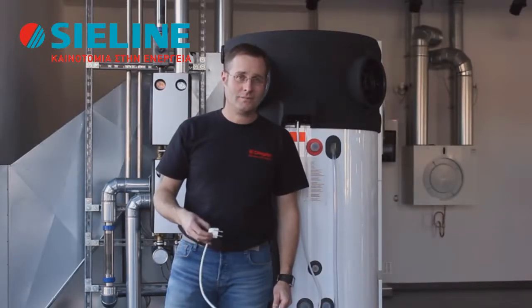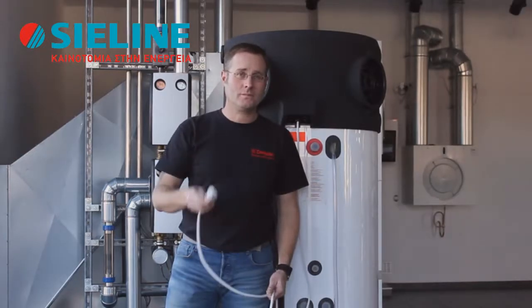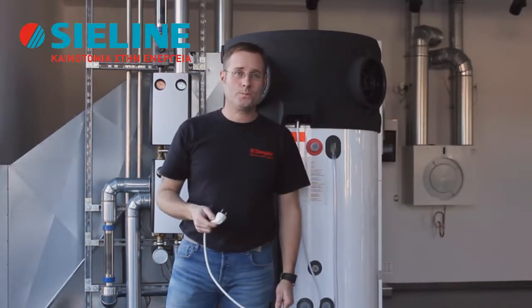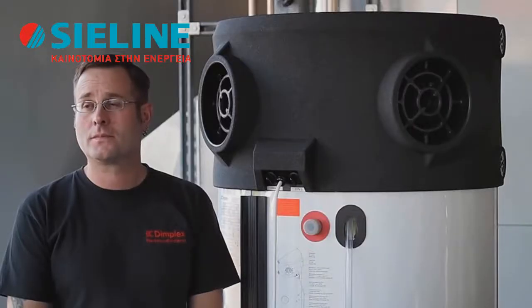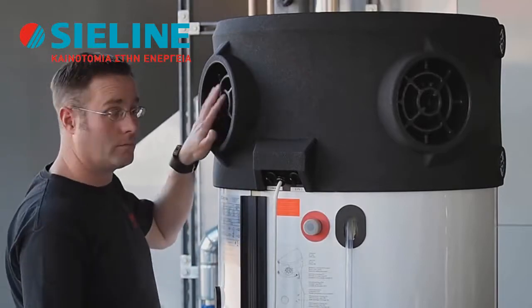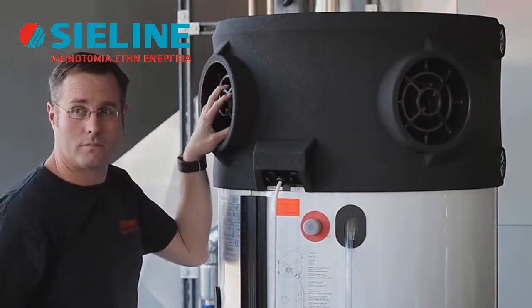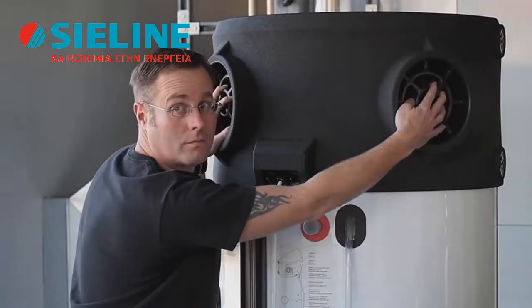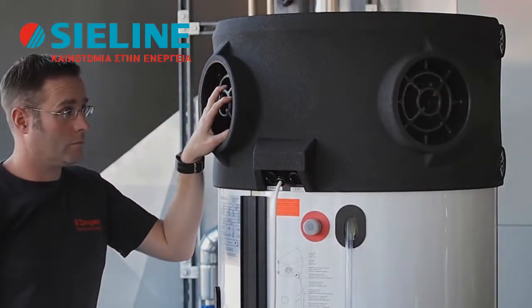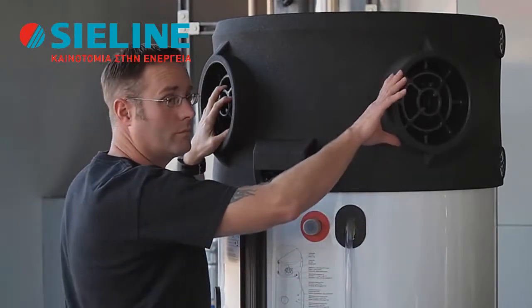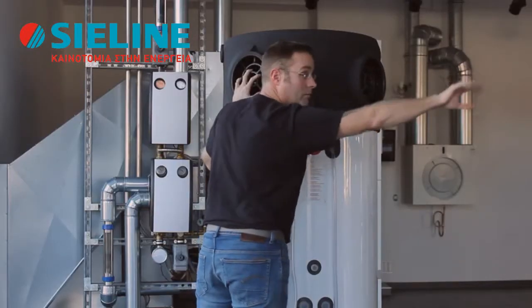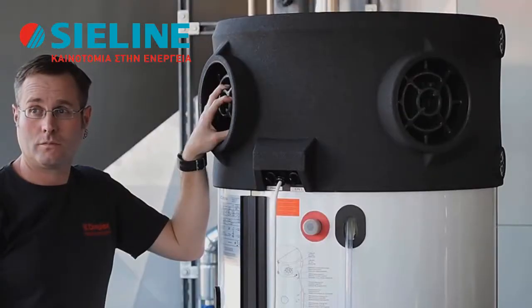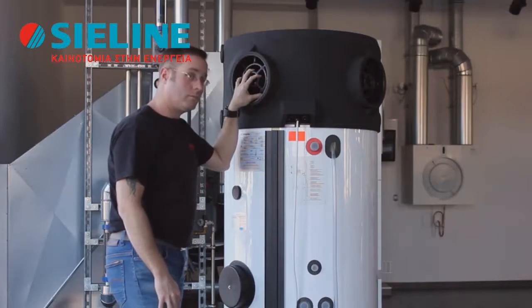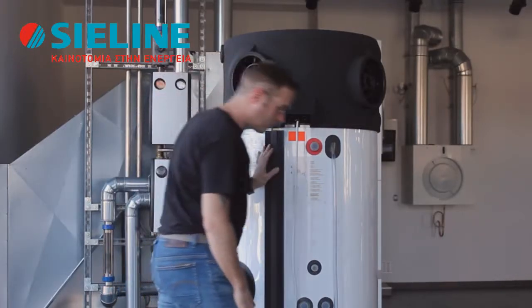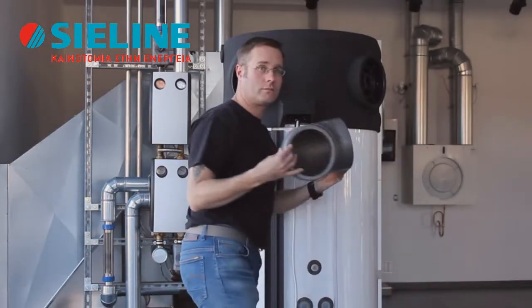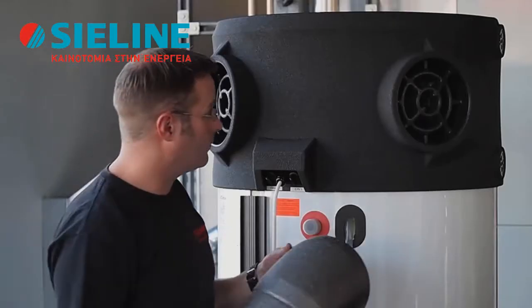When you use a plug for connection, please make sure that the socket is secured with a C13 fuse. On the top of the heat pump you can find the air inlet and outlet, whereas the outlet is always on the fan side. Please make sure that the air outlet is not routed towards a wall in order to avoid air short-circuiting. If you don't have any other choice and the air is routed towards a wall, then please use a 90 degrees air duct to avoid the short circuiting.